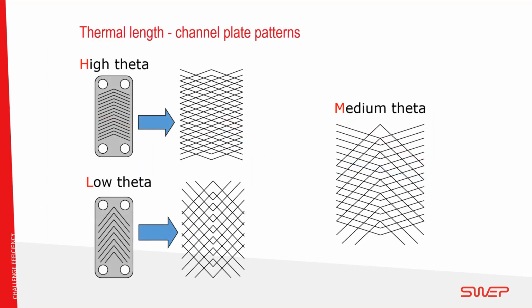So we address this with the pressing of the plates, and this characterizes the heat transfer performance, or what we call thermal length. A wide chevron angle shown at the top is a high theta pattern, and that's for cases that are difficult and require a large thermal length. On the other end of things, we have an acute chevron angle, or a low theta pattern, and this is where a small thermal length is required.